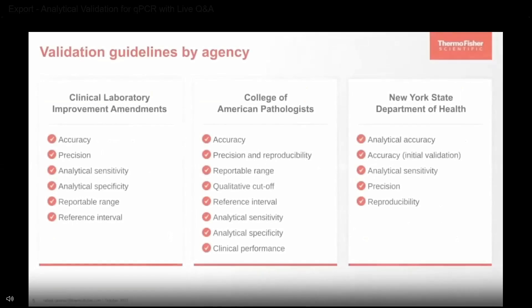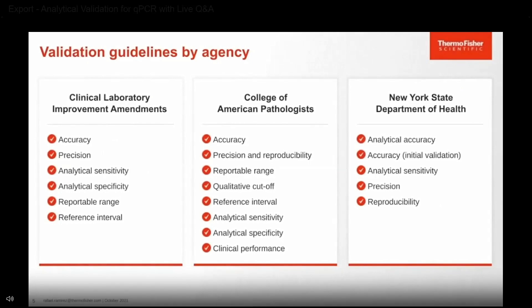Let's line up each accrediting agency and talk about their specific guidelines. From CLIA, they cover all the high-complexity laboratory experiments that need to be covered in a validation: accuracy, precision, analytical sensitivity, specificity, reportable range, and reference interval.